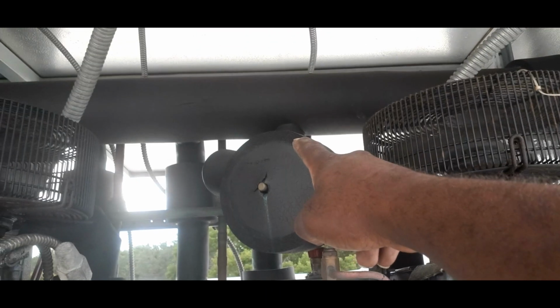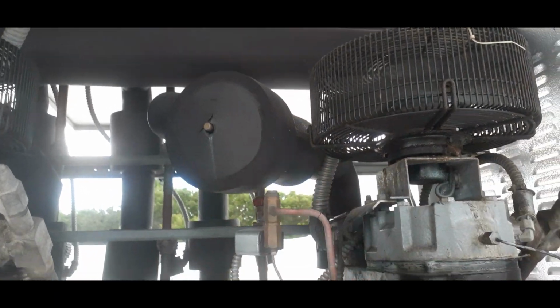But let's get our rack back down to suction set point. Case is good. Alright, so we got 0 gas on the rack. That's another reason sometimes that demand cooling trips. But I believe it tripped because we had hot gas just dumping into the compressor, literally right here, right behind that compressor. So it's gonna take the path of least resistance. Look right there. It's just gonna come right on in.